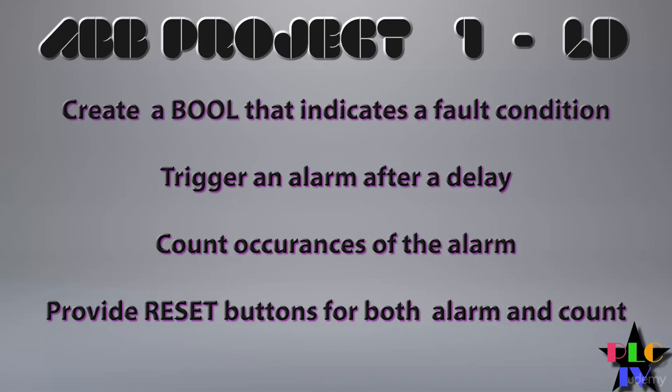After that, we do want to add one more layer into this cake. We also want to have a counter, which is going to count how many alarms we've had. We can count that up to like 100 alarms or something like that. So in your program, we want to be able to use an XIC — or in this case, it's going to be called a contact — with a time delay to create an alarm. We want to be able to reset that alarm once that contact is no longer closed. And even if it is closed, we want to be able to reset it, but then it'll re-engage after the time delay expires again. And then we want a counter which is going to be accumulating and counting how many alarms we've had, so we can keep rocking this alarm back and forth and watch the counter go up.